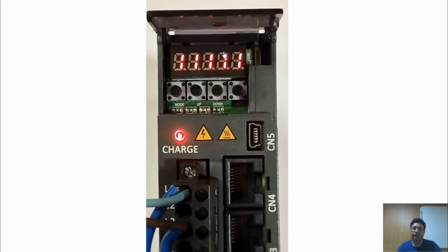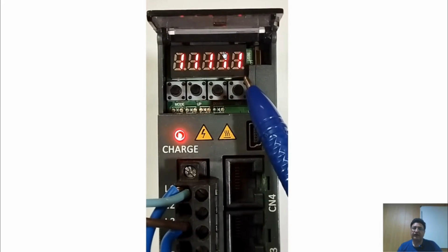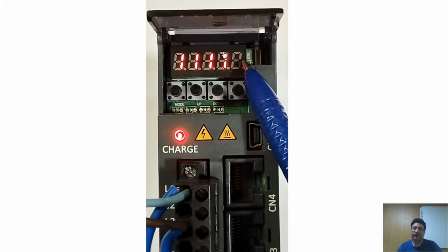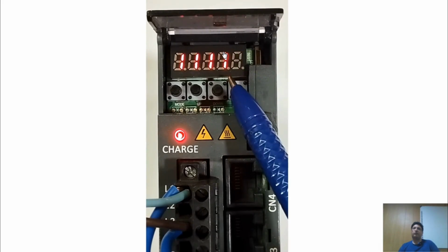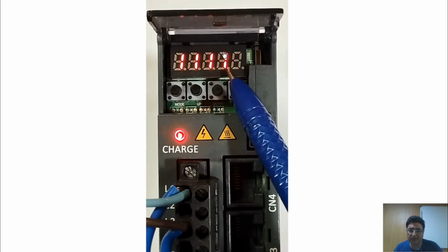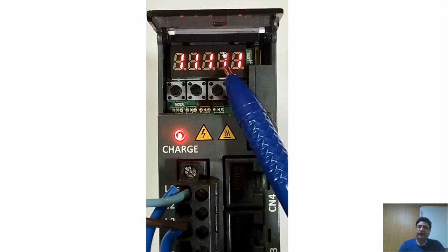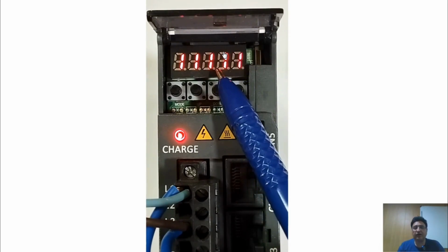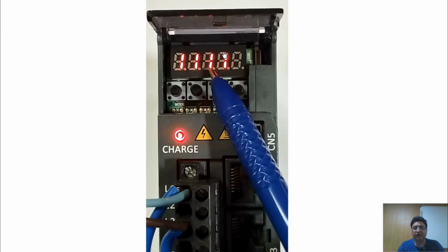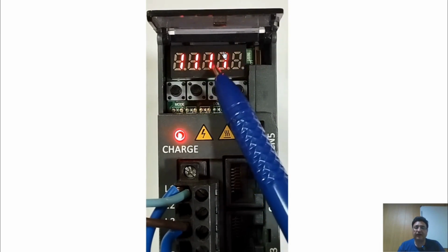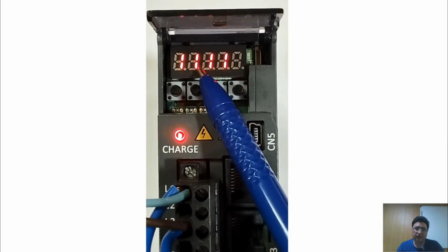Here as well, within this parameter, we can change the value of each individual digit, and for each of these digits displayed here, we can set the value either to 0 or to 1. If we set it to 1, it will operate in the normally open state, meaning the circuit is open under normal conditions, and if we set it to 0, it will operate in the normally closed state, meaning the circuit is closed under normal conditions.